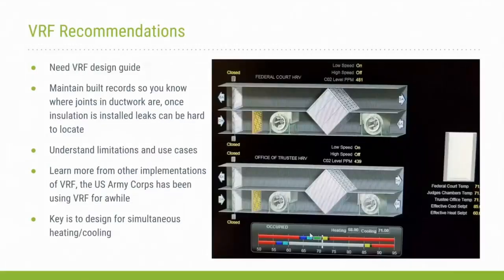So VRF recommendations. No VRF design guide is one thing I'm going to throw out. I can turn to my ASHRAE systems and equipment book, chapter 18, and you've got some guidance in the ASHRAE handbook, but there is no book that I can pull off the shelf that provides you the design guidance or install guidance. For example, there's a nice DOAS ASHRAE book that folks can reference. There's a nice chilled beam reference guide, and there's a reference for UFAD. So there's lots of guides out there that ASHRAE has produced, that technical folks have produced, but there's limited information about VRF systems. And I think that's something that the industry is having a problem with.